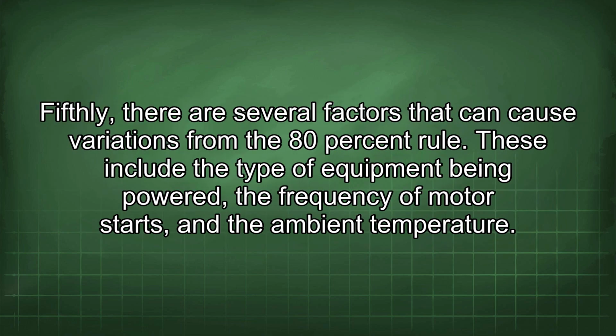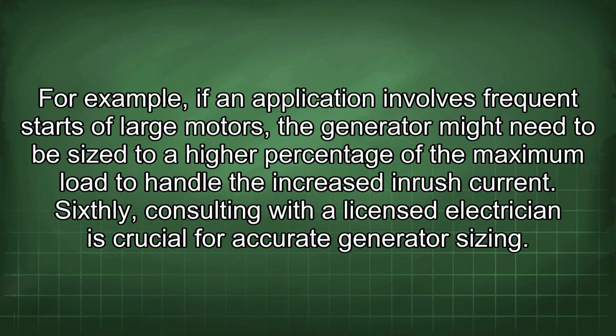Fifthly, there are several factors that can cause variations from the 80% rule. These include the type of equipment being powered, the frequency of motor starts, and the ambient temperature. For example, if an application involves frequent starts of large motors, the generator might need to be sized to a higher percentage of the maximum load to handle the increased inrush current.